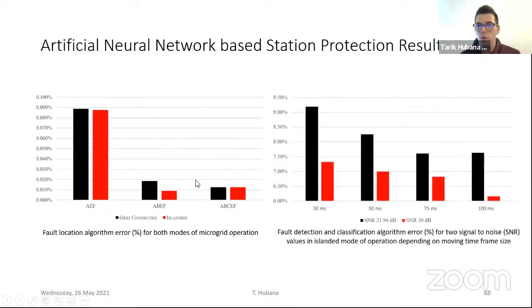And finally, for the fault location algorithm, on the left side, we see errors for 3 types of faults, since in this case, the accuracy did not depend on the level of the noise. And we see that the worst accuracy is below 0.1% for the single line to ground faults. And on the right-hand side, we see how the moving time frame size affects the accuracy as well. So basically, with the larger moving time frame, the accuracy increases, which means that we have more data and that the neural networks are capable to assess these data better. However, we do need to make a compromise if we want to have a fast reaction and a lower reaction time.